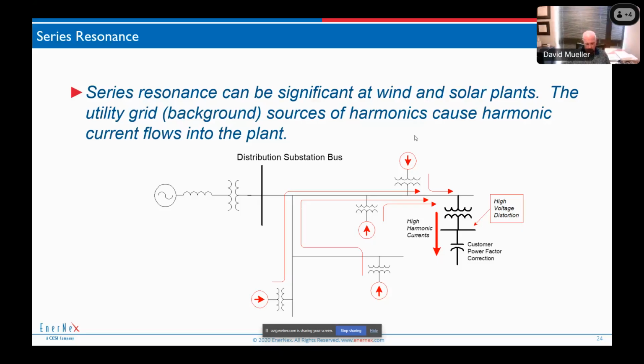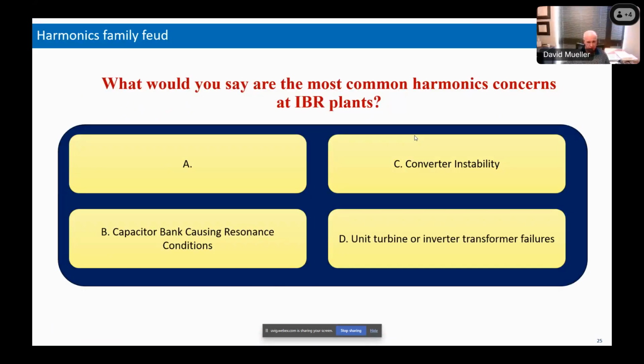Recently, at one plant that we were working with, they switched in the cap bank and things started making noises, and they burned up their AC unit inside the substation, and they had other failures of some of the converter electronics and other types of things. So these can be quite serious problems. So capacitor banks really need to be studied. Most of the time, the resonances are out of harm's way, but if the resonance is close to the fifth or close to the seventh harmonic, that's very typical for a transmission system background source, then that can be identified as a potential problem. So that's capacitor banks.